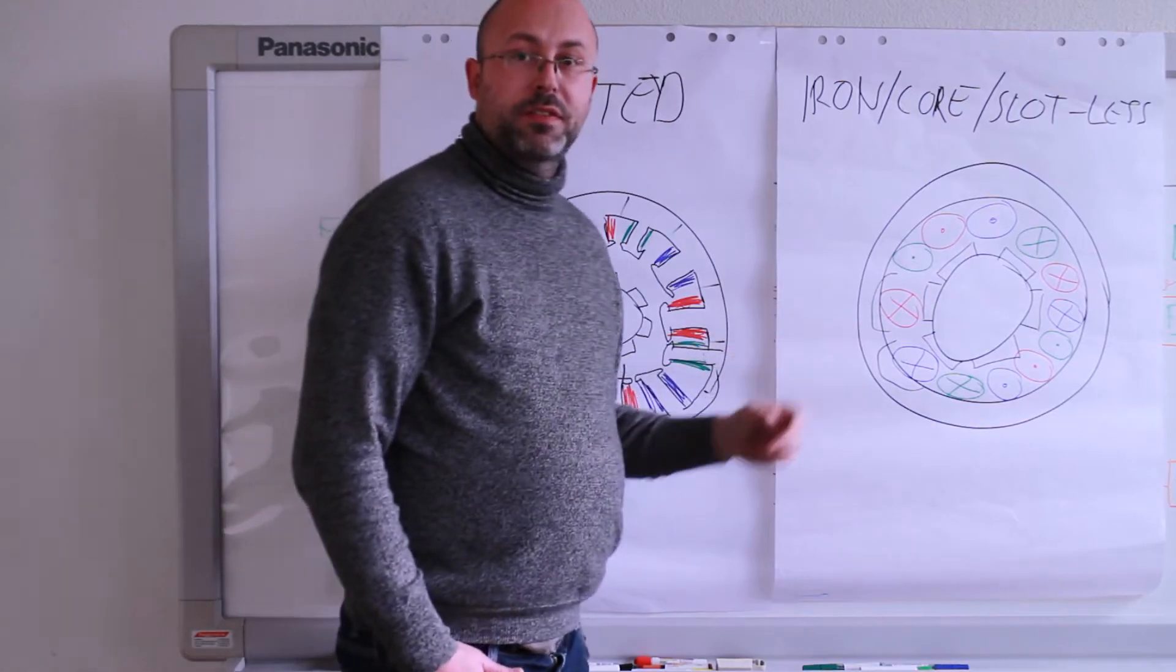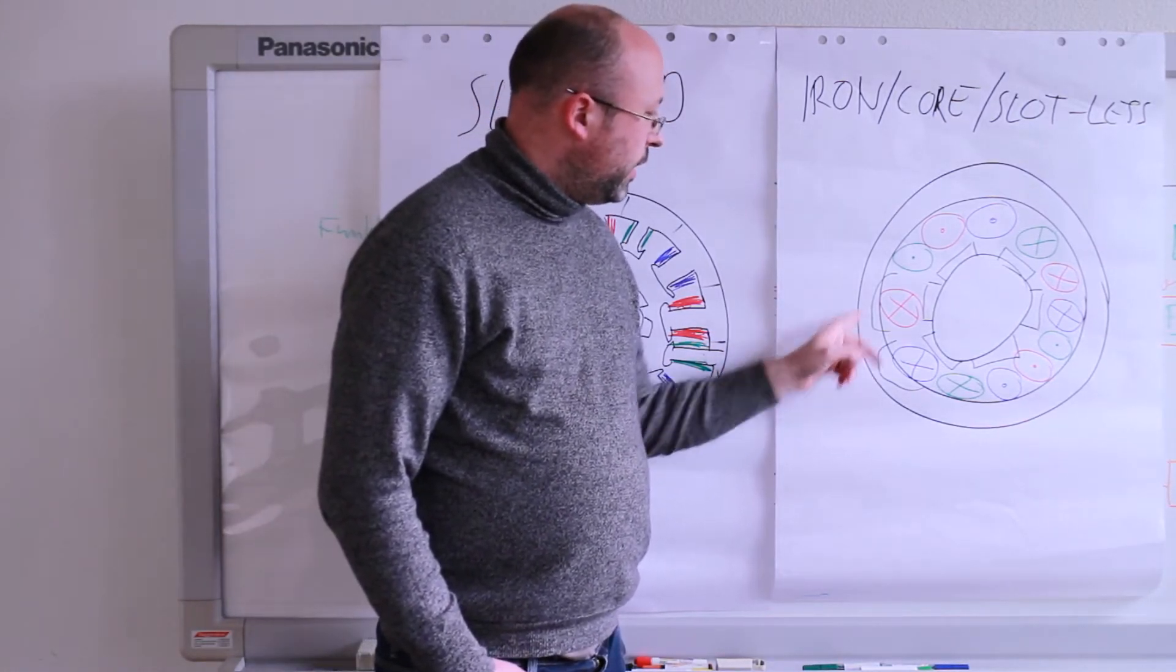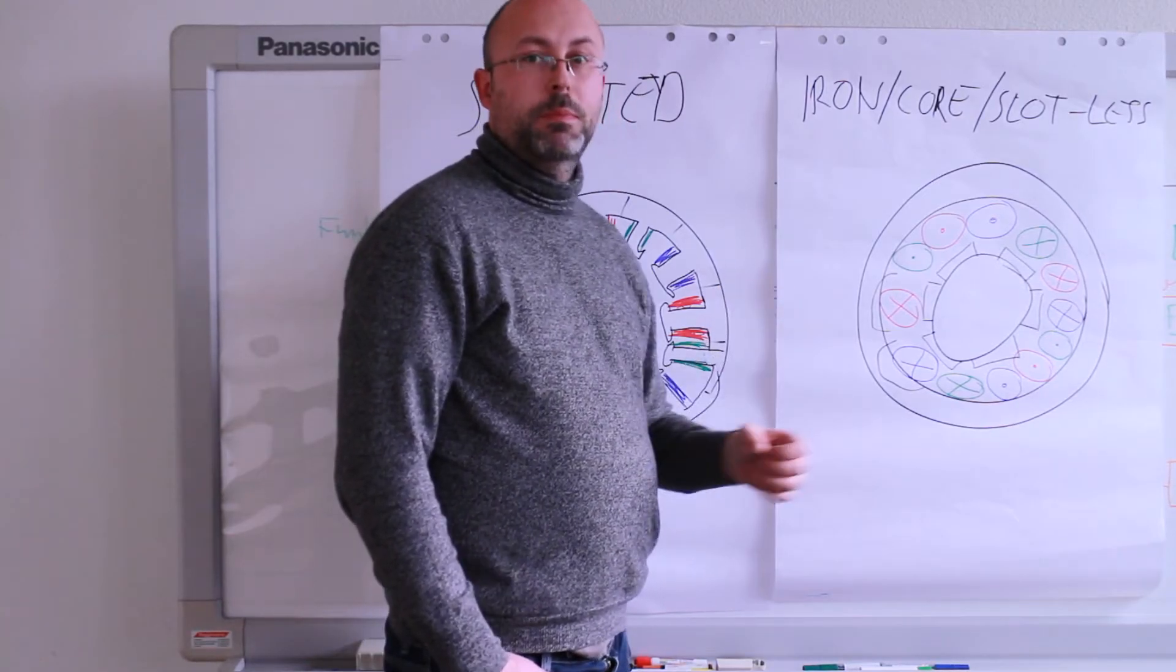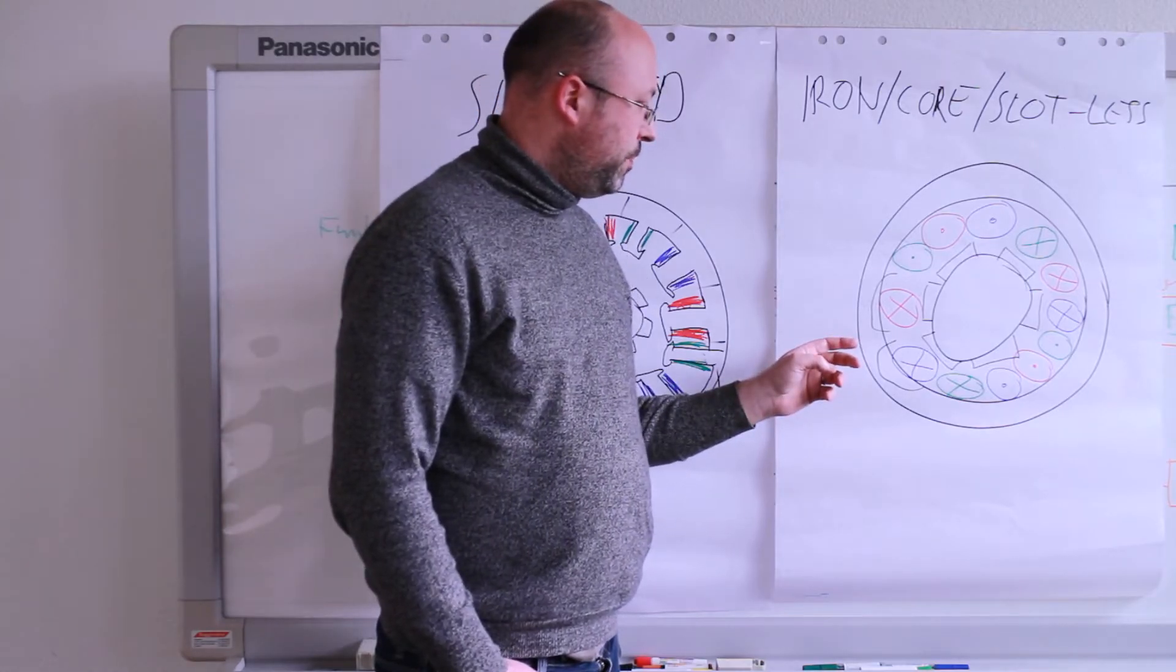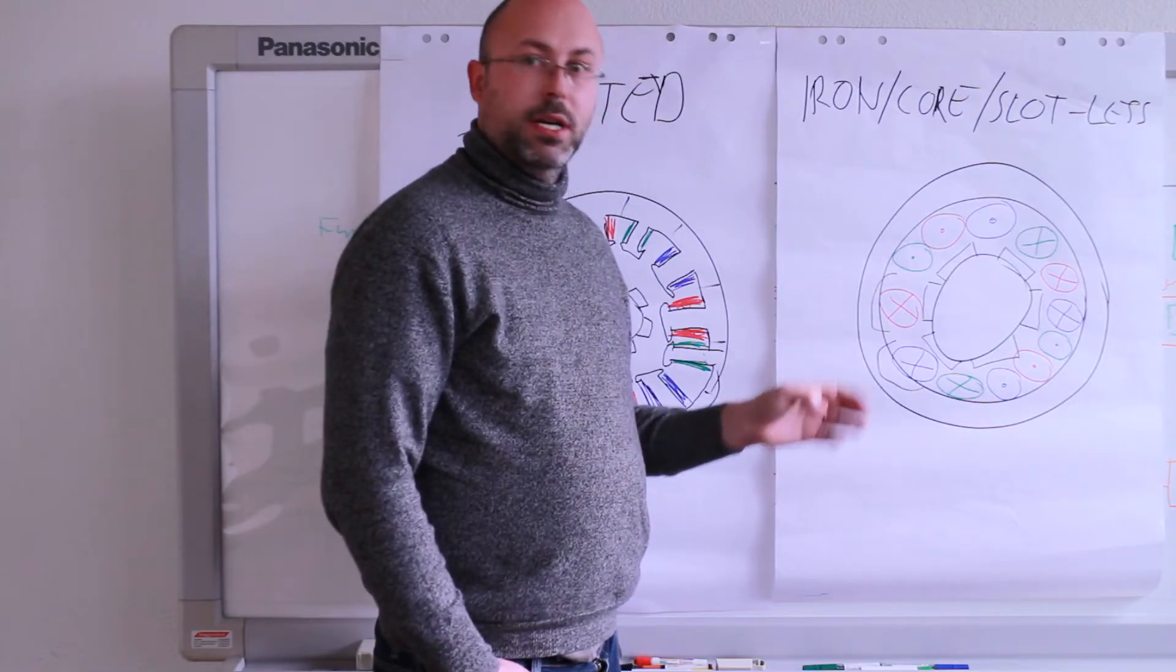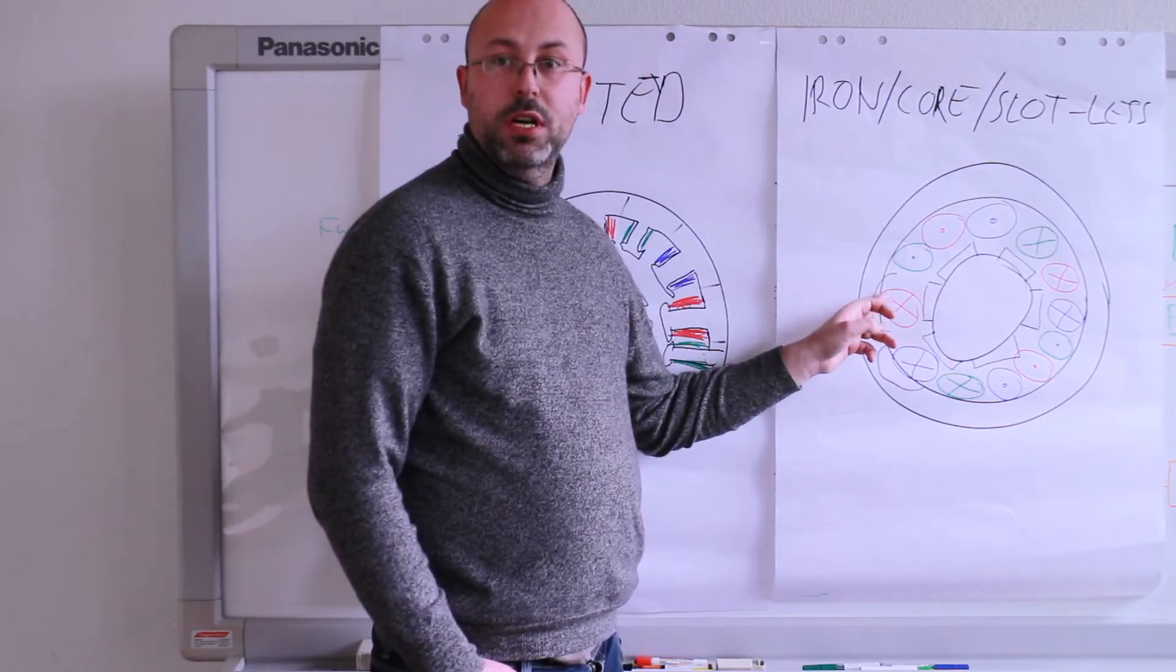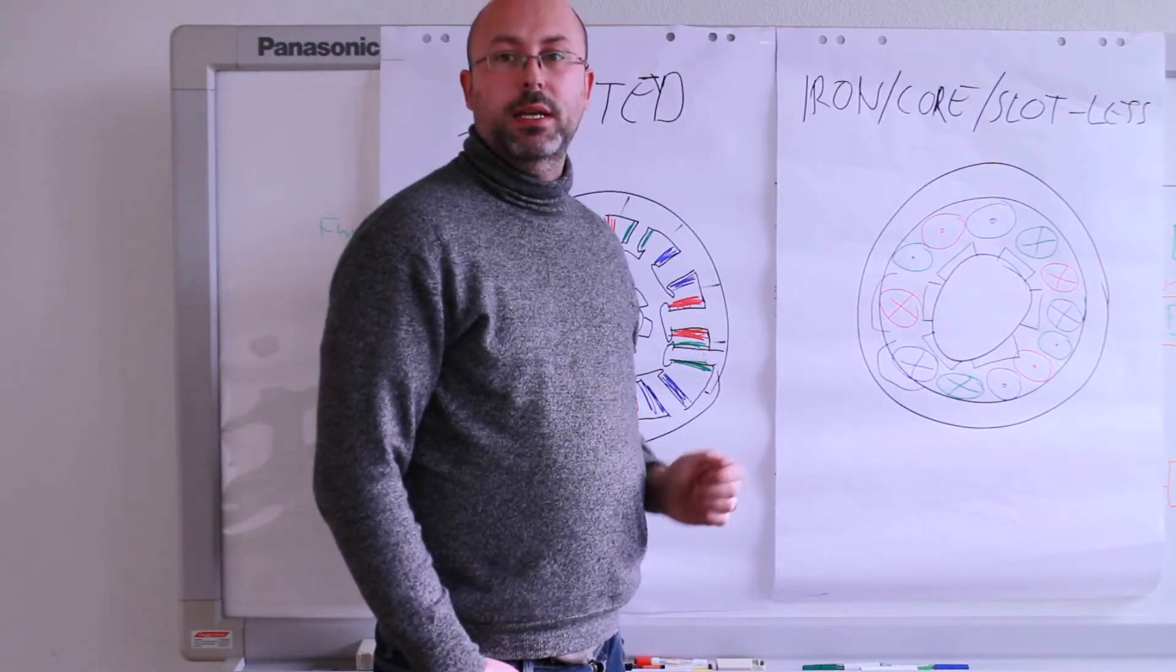The advantage from a manufacturing point of view is that stamping a round piece of sheet metal is way easier. You just get a standard punch, a standard cutting die for punching. If you want to make different sizes of motor and you organize it neatly, you could even cut the next dimension and the next dimension of motor out of the same piece of sheet metal with nearly zero losses.